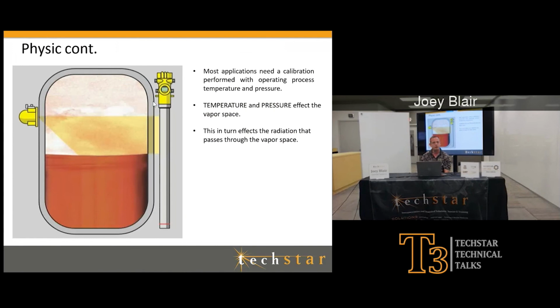When we do our calibrations, whatever vapor you're running, we want to be at process conditions, usually during startup. So let's say this vessel has 100 pounds of vapor on it. We'd like that same kind of vapor, because different vapors have different densities. The closer we can get to the real densities in our vapor space, the better.